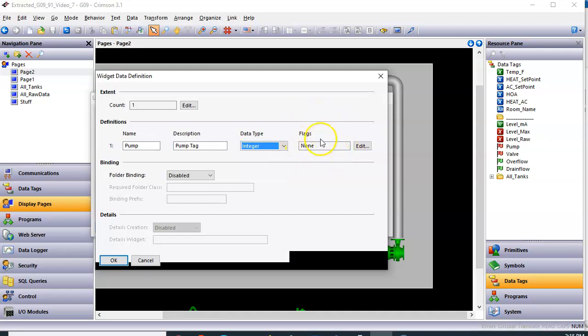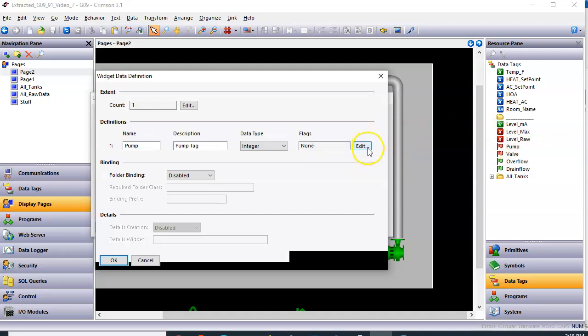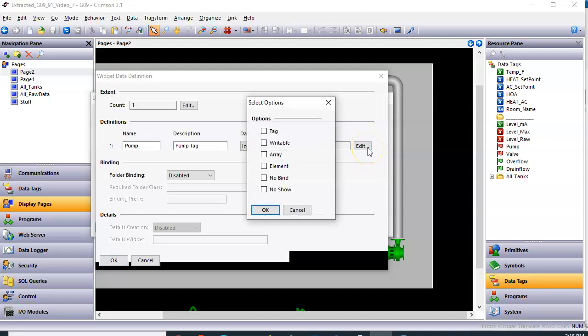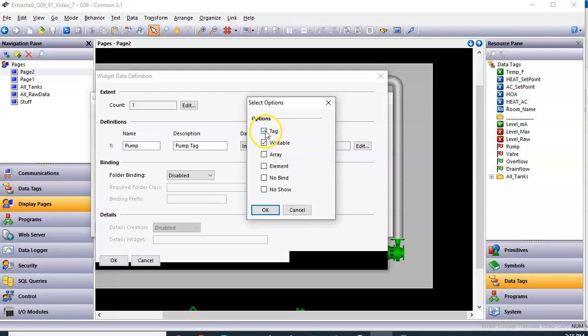And then the flags category basically says, how will this pump tag interact eventually with the real world tag? Well, since this guy is red, that means it's writable. So I'm going to hit the edit button here. I'm going to choose writable. But then of course, I want this to show if something else ever changes this in my code, I want this to show. So the word tag here, I wish it had like a hyphen readable here, because that's what that means. So that makes it readable and writable. So we'll click OK.